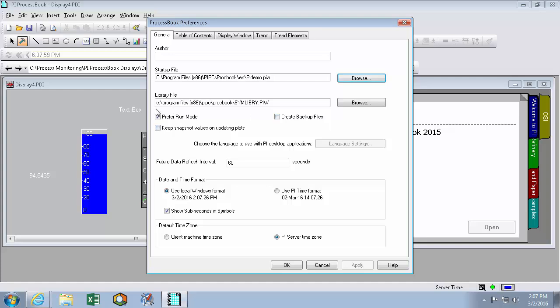Another option of note on this page is the Prefer Run Mode checkbox. While Prefer Run Mode is checked, anytime you finish building a symbol in Build Mode, you'll automatically return to Run Mode. Additionally, anytime you open up PI ProcessBook, you'll also find yourself in Run Mode. If you plan on building a lot of symbols or displays back to back, I'd recommend taking Run Mode off. But if you're intending to just consume displays, preferring Run Mode is ideal.